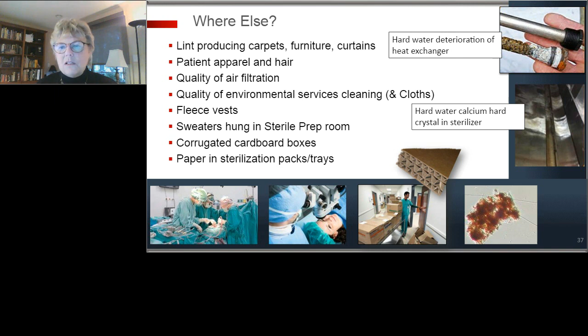Clean with low-linting disposable rags and low-linting apparel for housekeeping staff. Use a wet vacuum whenever possible, never dry sweep. You must clean before you disinfect, and leave the disinfectant wet for the full contact time stated on the IFU—something we forget at home too. It can't disinfect an area if it isn't on there long enough.